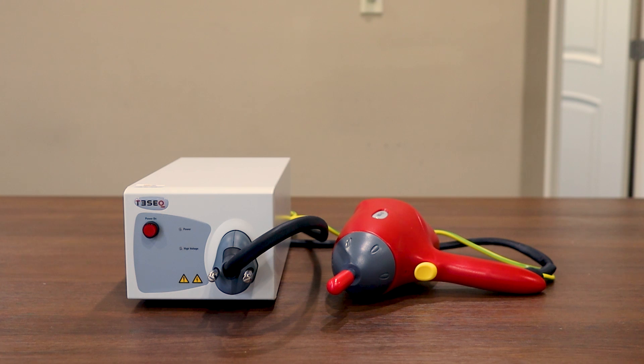As we're going through the video today, we're going to be referencing the data sheet and user manual, which I'll put a link for in the description below. The Teseq NSG437 is designed for 30kV air and contact discharge testing and allows for networks to be easily swapped out. It includes both the air and contact discharge tips as well as a 150 picofarad 330 ohm network designed for IEC 61000-4-2.